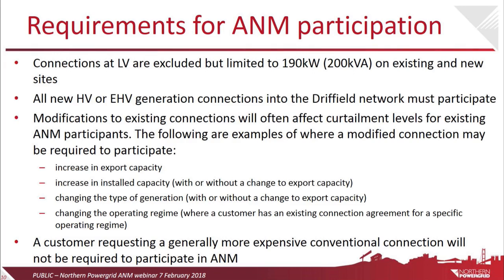There are other reasons why the level of curtailment might change in future, such as the take-up of low carbon technologies by domestic customers. For example, I mentioned more solar domestic PV could worsen curtailment for customers that are in the ANM scheme. But conversely, if we see a large uptake of electric vehicle charging in and around the Driffield network, that would increase the demand on the network, the consumption of electricity, and that could effectively improve the curtailment that customers in the ANM scheme will be subjected to. Worth pointing out though, if you do decide to connect and contribute towards reinforcement, you won't have to participate in the ANM scheme itself.